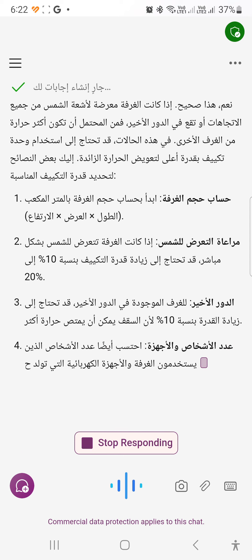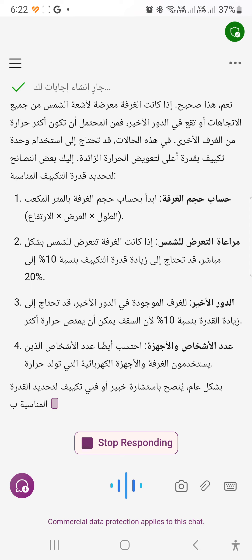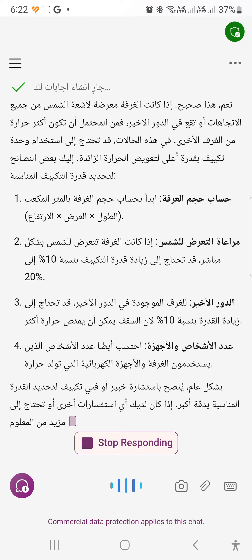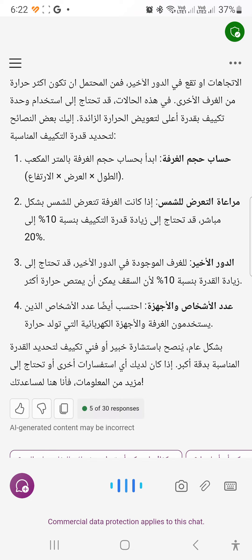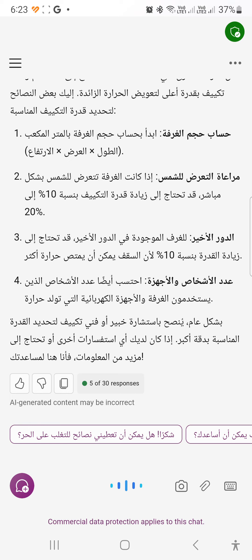When calculating room volume for AC sizing (Hajim alhrafa), you must account for the actual dimensions — length, floor area, and ceiling height — as well as sun exposure. Direct sun exposure can increase AC power requirements by 10% to 20%. Rooms on the top floor may need up to 10% more capacity since the ceiling absorbs more heat. The number of people and devices should also be calculated. It is advised to consult a specialist or AC technician for accurate capacity estimation.